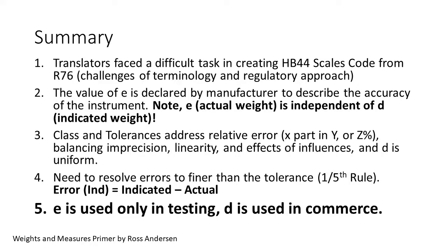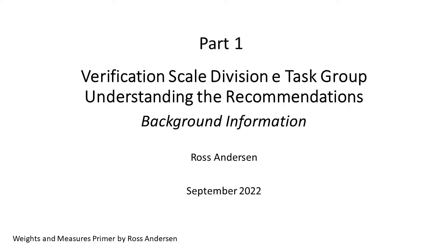Point five: E is a tool only for testing, not the object of the test. Test loads and tolerances in R76 Table 6 are in E's. The tests verify the accuracy and consistency of the D's. Once the instrument is verified as compliant, the weight indication of the instrument in D's is used in commerce. This brings my discussion of fundamentals in Part 1 to a close. Please come back for Part 2, where I discuss the task group recommendations, and Part 3, where I'll discuss two case studies applying the principles of the scales code. Thank you for watching.